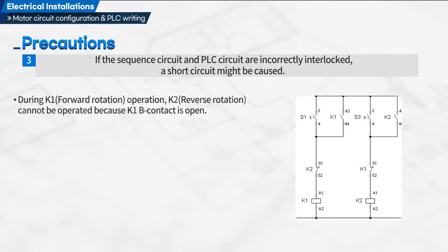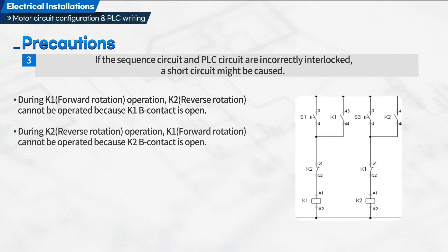During K1 forward rotation operation, K2 reverse rotation cannot be operated because K1 B contact is open. This describes the interlock circuit configuration.